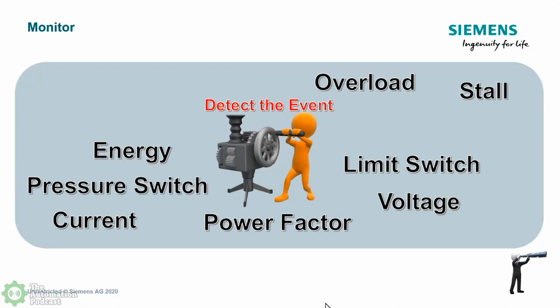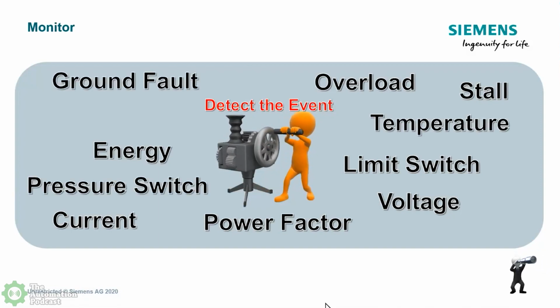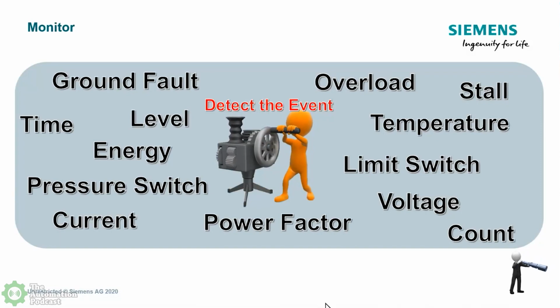But here's a list of some of the stuff that we can detect within SIMOCODE. Of course, as I stated, we can do overload. That's the basic property of it. It is your overload. But then I can monitor current and do current only if that's your requirement. But then I can also add or change the current CT to a PT-CT, which is your current transducer and power transducer in one. And now I can do phase loss, phase imbalance, and monitor the voltage. And then I can also add to the basic SIMOCODE up to 6 RTDs and bring that into the SIMOCODE, where I can put them on a gearbox housing or a pump housing and be able to monitor the temperature.